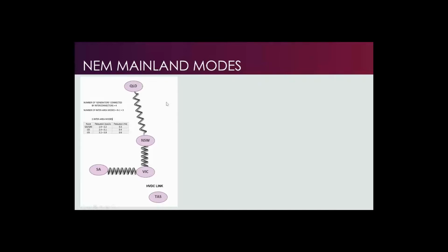These 3 modes are called I20 or QNI, I25, so 2.5 radians per second, and I35, 3.5 radians per second. By the way, radians is 2 pi f, so you can calculate frequency easily from that. QNI mode has the lowest frequency and the weakest damping. Without stabilizing devices, it would be unstable.